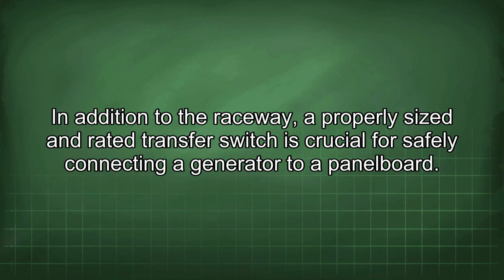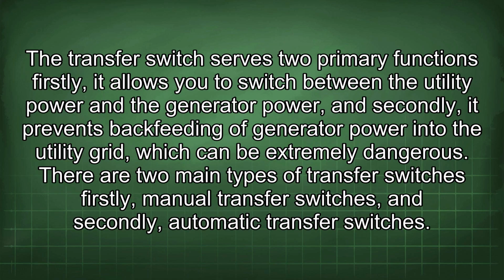In addition to the raceway, a properly sized and rated transfer switch is crucial for safely connecting a generator to a panel board. The transfer switch serves two primary functions. Firstly, it allows you to switch between the utility power and the generator power, and secondly, it prevents backfeeding of generator power into the utility grid, which can be extremely dangerous.